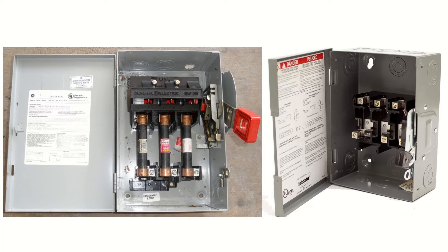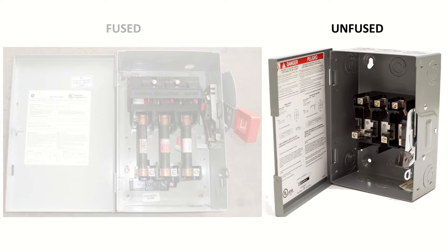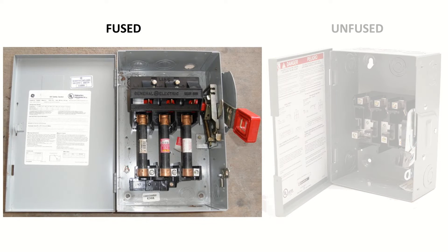There are essentially two types of disconnects: fused and unfused. Unfused safety switches provide no circuit protection, with their sole purpose being a means to open and close the circuit. Fused safety switches, on the other hand, combine the switch and fuses into a single enclosure to provide that extra level of protection against overcurrent and short circuits.